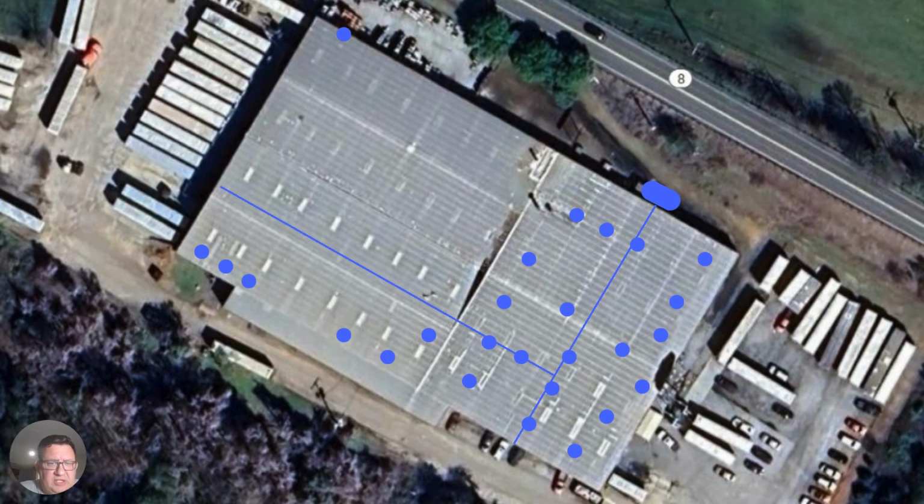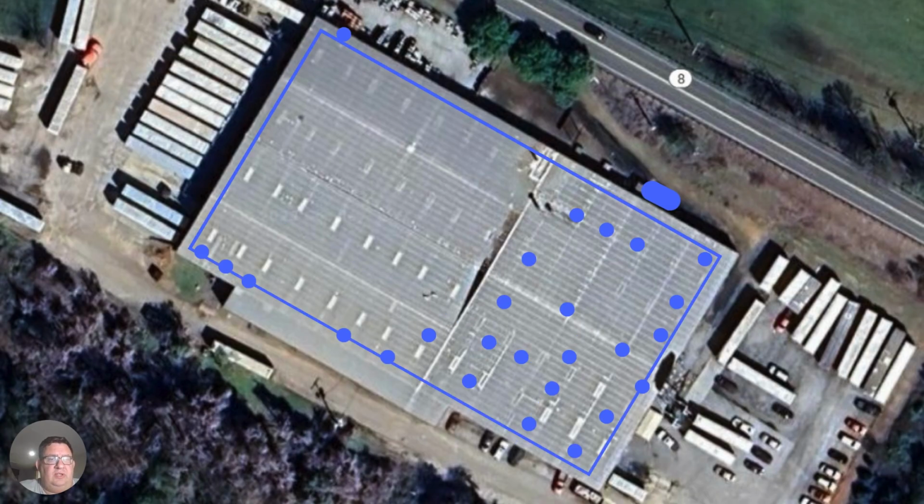So some people might say, well, then let's consider doing a loop design. Well, if we're going to do a loop design, then we would find a position going around the facility, and this would give us 2 points of contact to each process, and then we would tie in the individual processes from there. This, oversimplifying, I guess, would theoretically cut the pressure drop in half based on a couple things that we really just don't know, nor have we stated in this case.